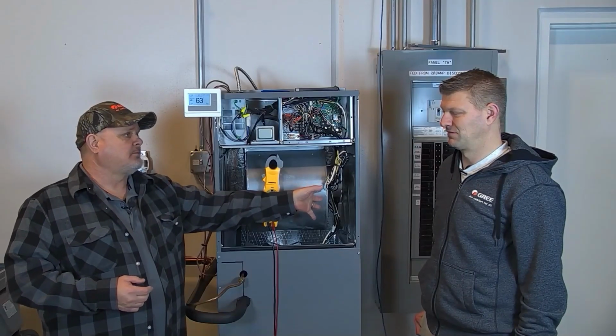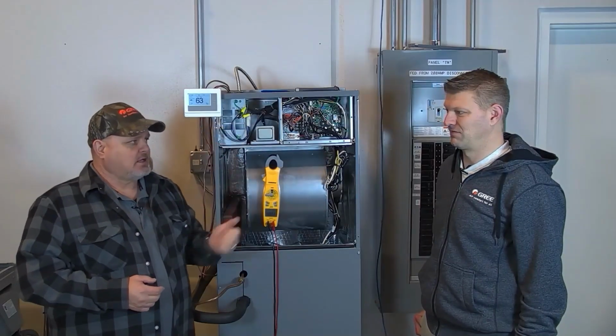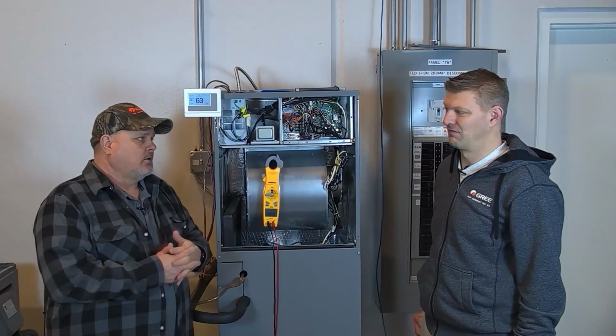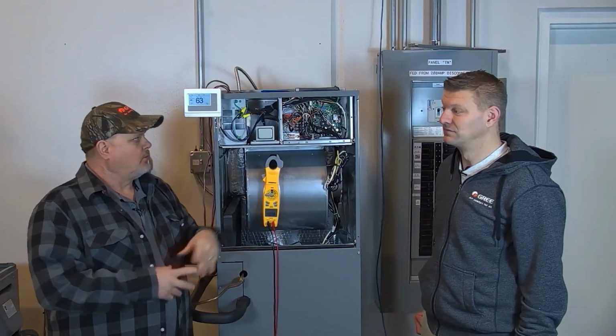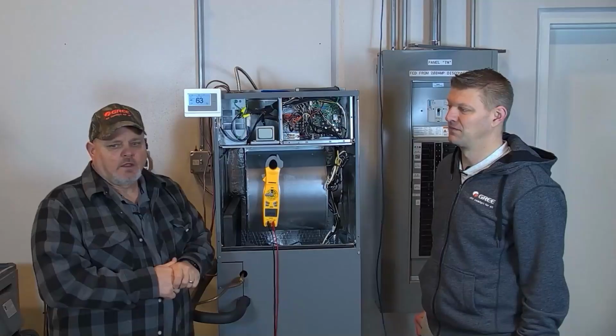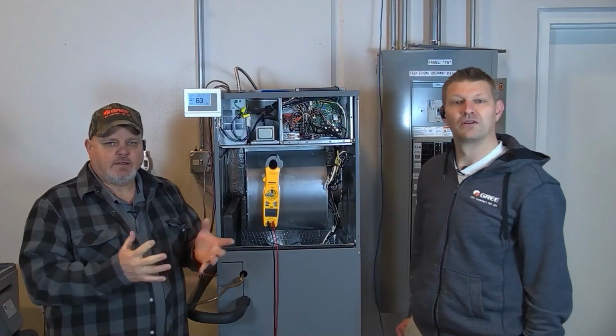Yep. So the only way you can really test this is: is the board doing what it's supposed to be doing to send out the signal to tell the motor to run? And maybe it is. The only thing that might have failed is the module not sending the feedback. Either way, it's still a bad motor, right? Right. But if you're getting the pulse out of the board and the steady 15 volts, then it's not the board. You've got a motor problem. Yep. Okay, well, with that, we're by your side. We're by your side.